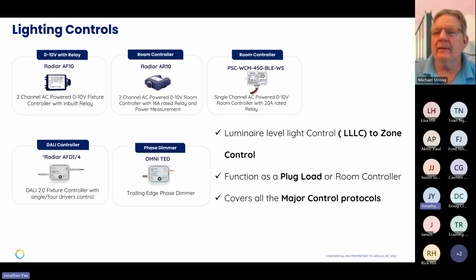For EM, we have a separate device called an RIB from Functional Devices. You're able to add this device into the EM system, where the EM line connects to the RIB and the normal line also connects to the RIB, and you can control both EM and normal lights using one of our PSC 450s or room controllers. If the building power goes off, the RIB will ensure the EM powers the emergency lights only, and the normal lights stay off because they have no power. But also the EM lights will be at 100%. That answers your question.